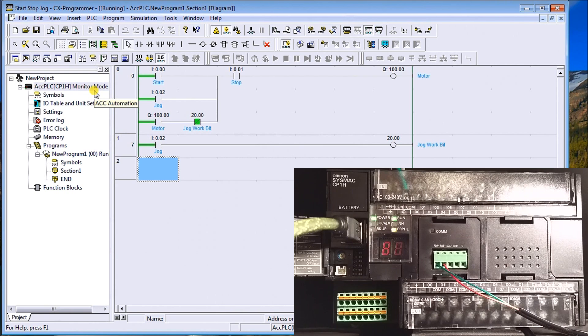In monitor mode, really nothing has changed in the PLC itself, but your logic is still running — your I/O will be updated. The CPU status can be monitored, and you can also force things on and off, reset them, and modify set values and present values of timers and counters. This mode is used for system adjustments. Program mode completely stops the CPU — logic will not be executed, user programs can be created or modified, memory can be cleared, and programs can be checked.